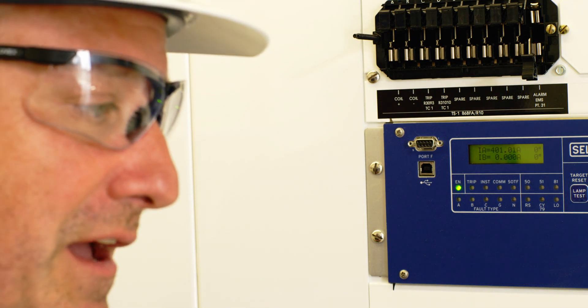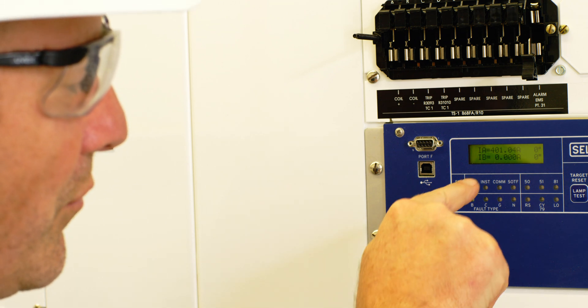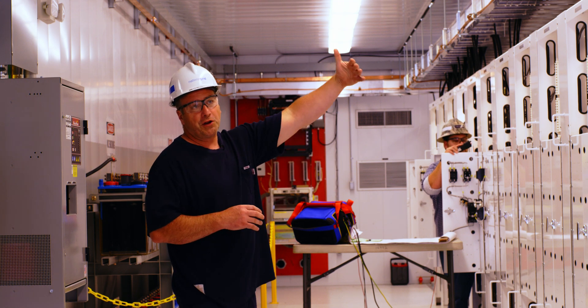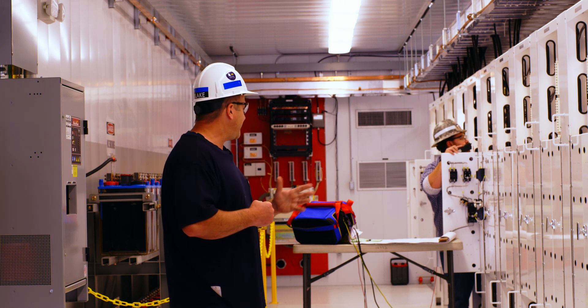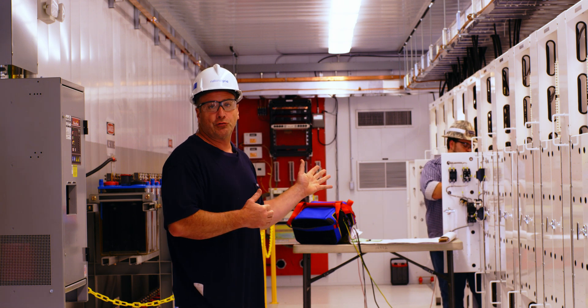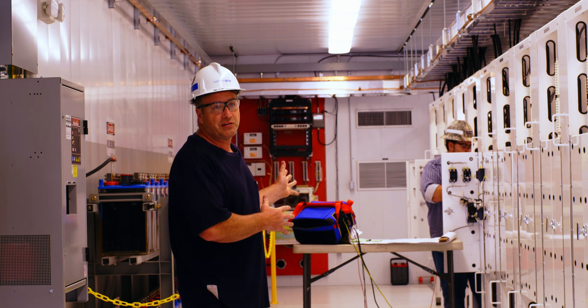It's a 2000:5 CT, 400 to 1 on the secondary side. So we've got 1 amp coming in to our relay and it's placed as 400 amps. Derek just finished checking our bus pots from out in the yard into the control house with the CPC 100, with easy access going from current to voltage. Now he's working on the DC control circuit doing the same thing — and it's also very nice. We did three different tests and used the same piece of equipment.